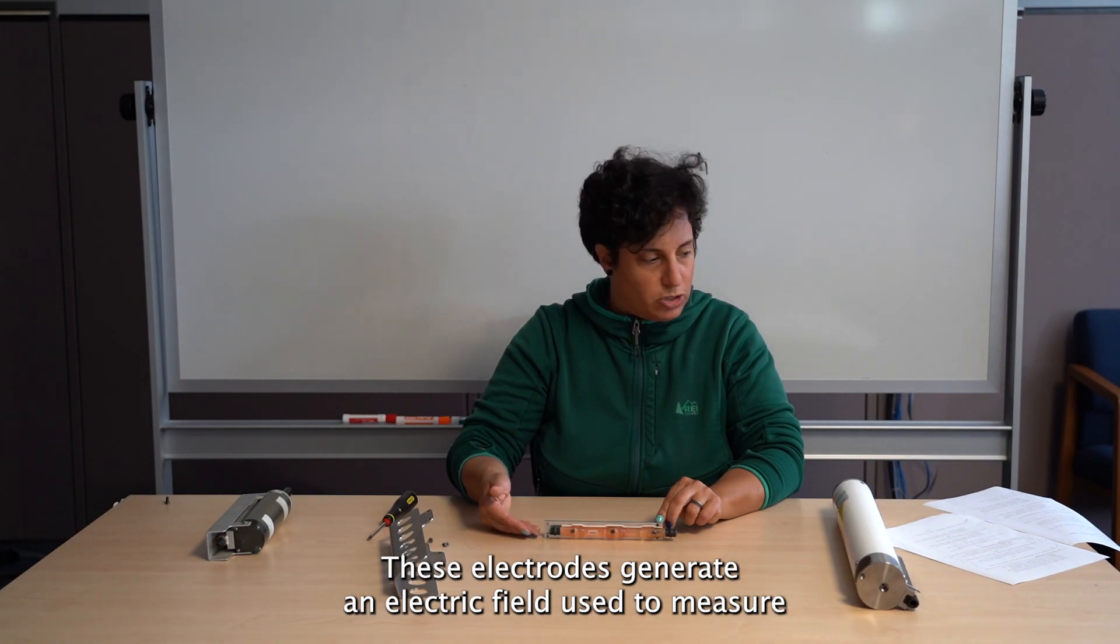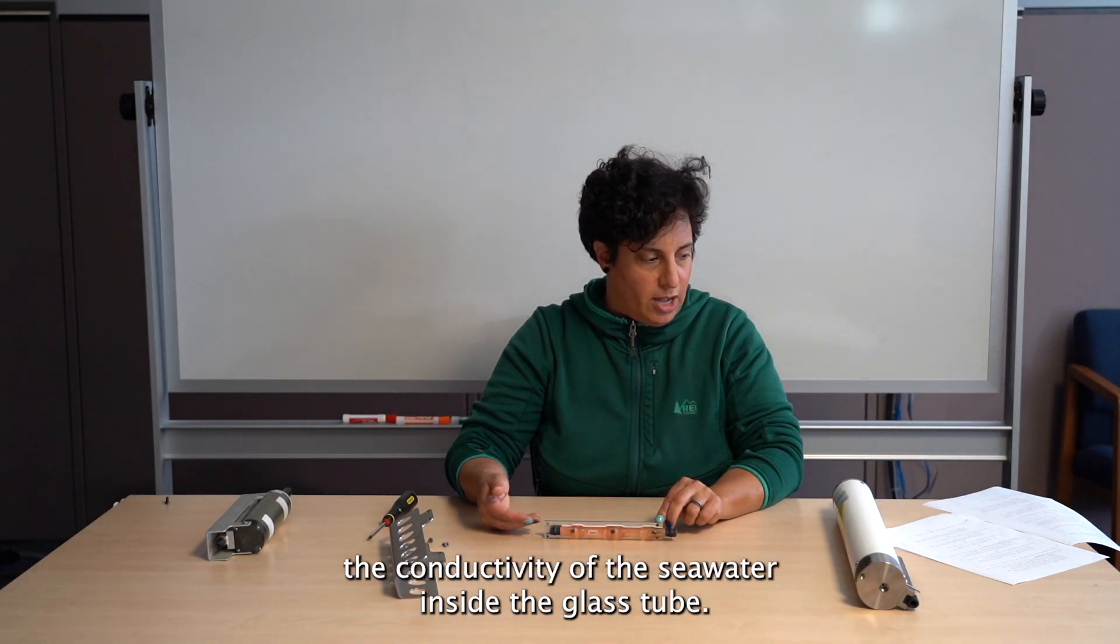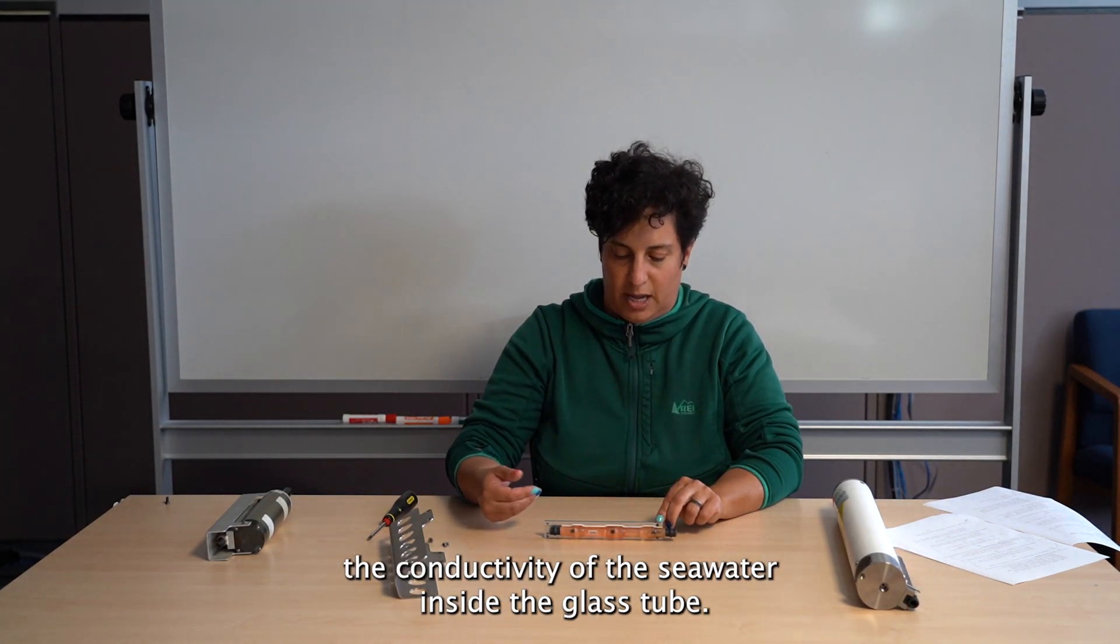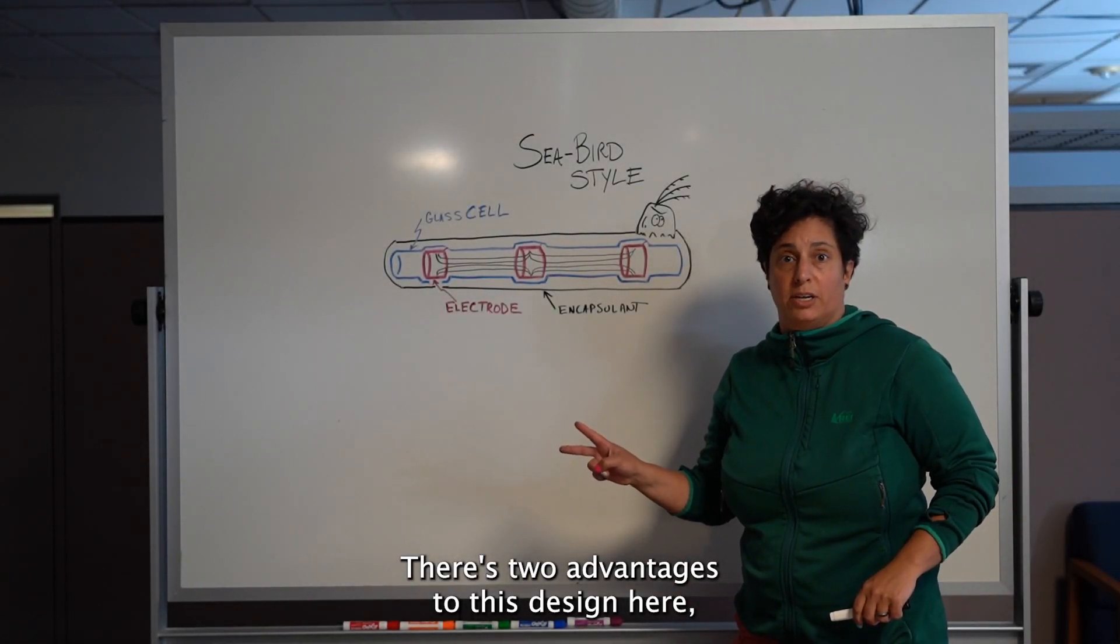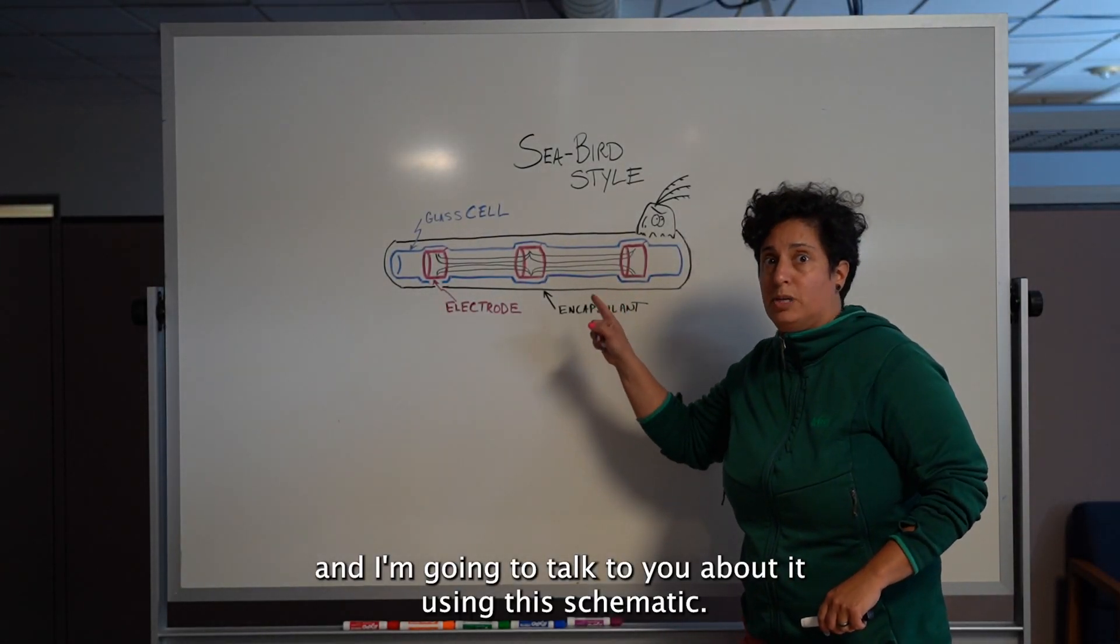These electrodes generate an electric field used to measure the conductivity of the seawater inside the glass tube. There's two advantages to this design here, and I'm going to talk to you about it using this schematic.